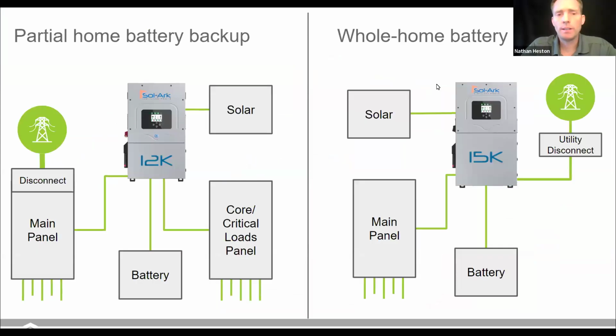So I'm going to highlight two different installation options. One is a partial home backup system. With a Sol-Ark 12K, you're limited to about 9 kilowatts of maximum sustained power. It can surge for a short time to start things like a well pump, but in general you wouldn't be able to back up your whole home with a 12K.